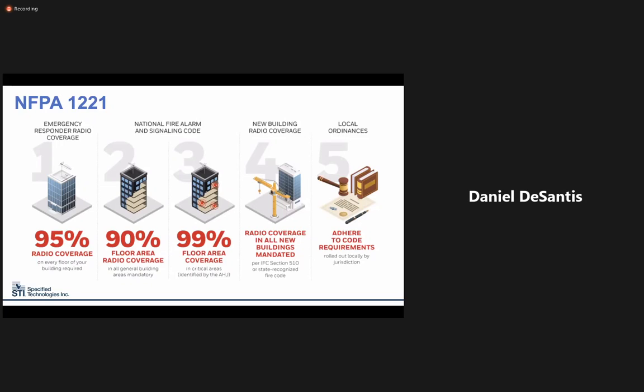Let's talk a little bit about wireless coverage. In the same way we need a router at home for our Wi-Fi internet signal to cover our houses, in-building wireless communication systems rely on strategically placed emanators and repeaters in order to cover a required square footage of a large building. NFPA 1221 stipulates that no less than 95% of the building's general square footage must be covered with such a signal. No signal means no communication, and in the event of a fire, that could translate to loss of life.